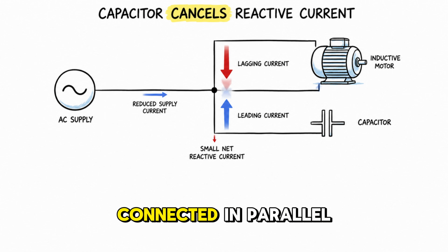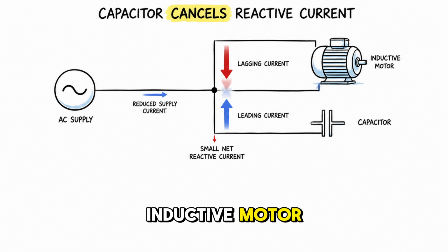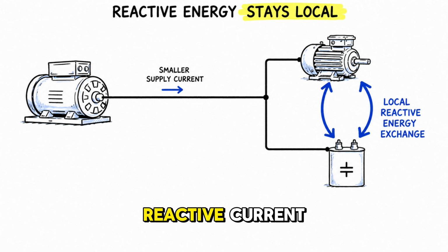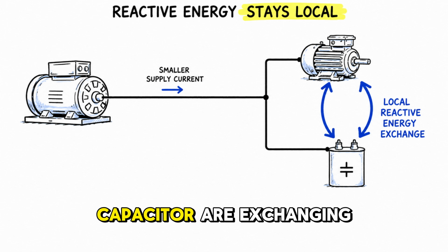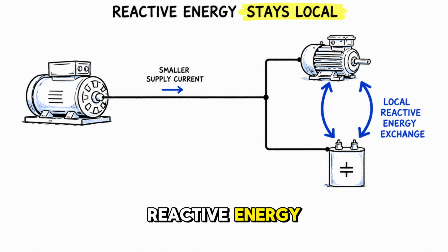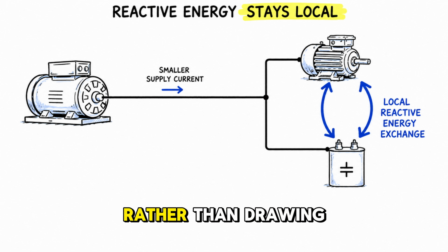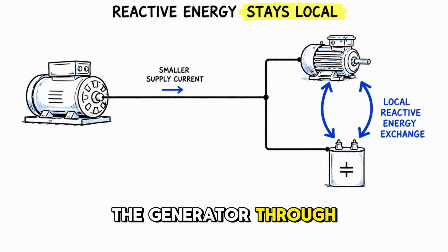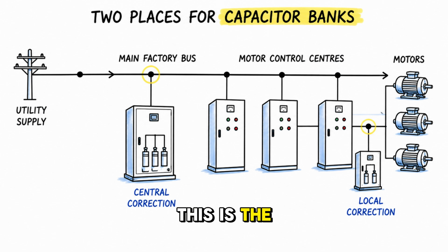When a capacitor is connected in parallel with an inductive motor, the leading current of the capacitor and the lagging current of the motor partially cancel each other at the supply terminals. The supply no longer sees the full reactive current, because the motor and capacitor are exchanging reactive energy locally between themselves, rather than drawing it all the way from the generator through the supply cables. This is the principle of power factor correction.